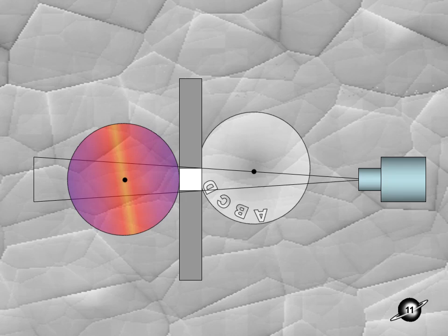At the same time, the X-ray film also rotates and passes through it. So image B is superimposed on the X-ray film. Then again, once B is superimposed, the object rotates again. Image C comes near the collimator, and image C is superimposed on the film. Since both the object and the film are moving in opposite directions with the same speed, the exact ABCD images are superimposed on the film as ABCD.